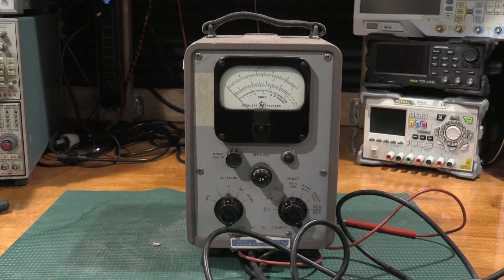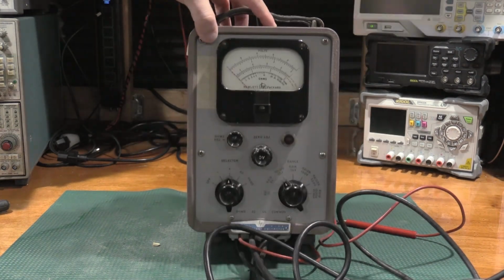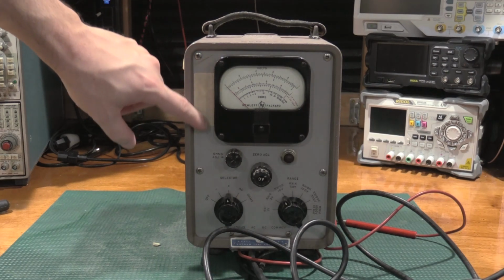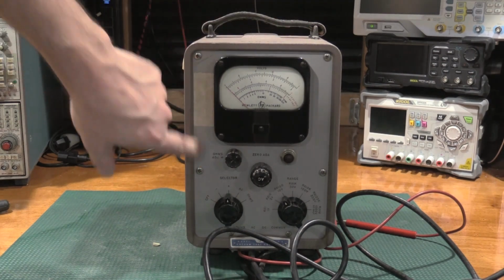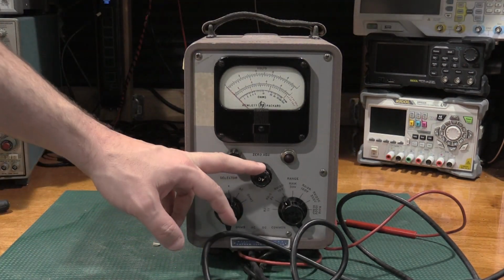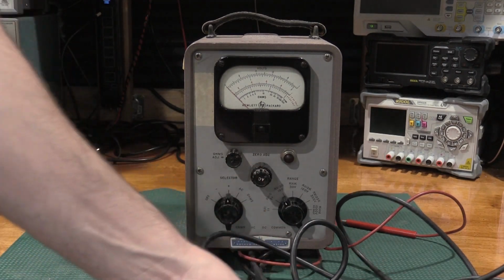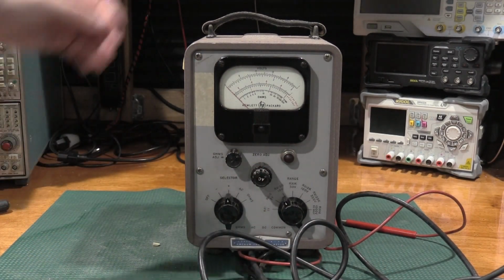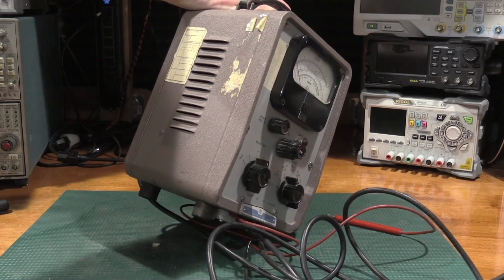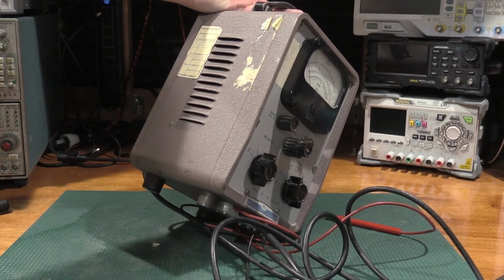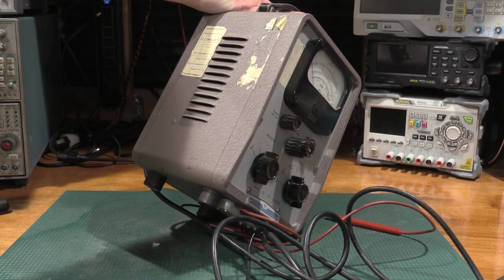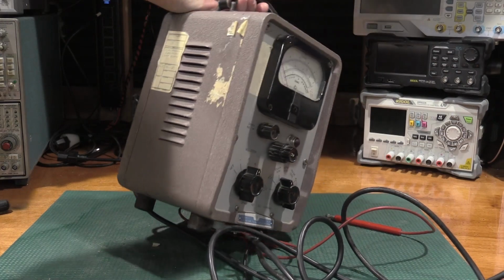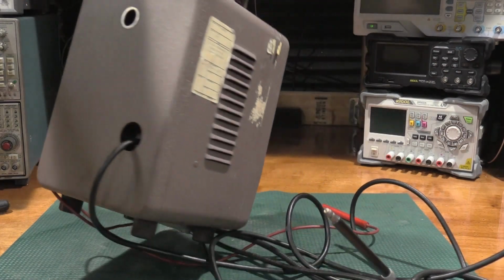This one's a little bit rougher shape than the 412. It's been used a little bit more. I'm going to need to clean this up a bit. Still in really good shape, just needs a bit of cleaning. The probes need some cleaning and things like that, but let's see if we have anything. This has a calibration exemption on the ohm scales and was last calibrated in '87, so it's been a while.